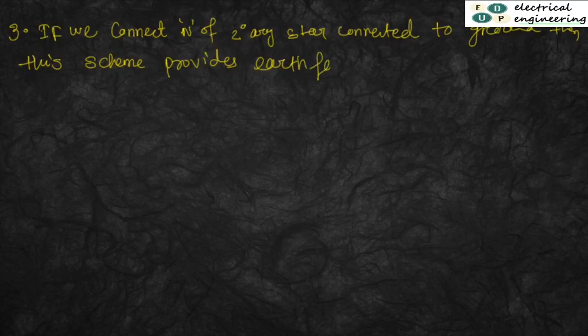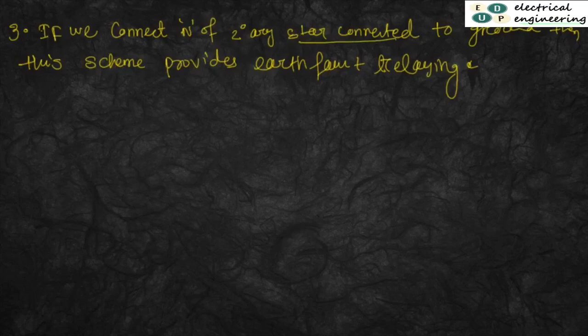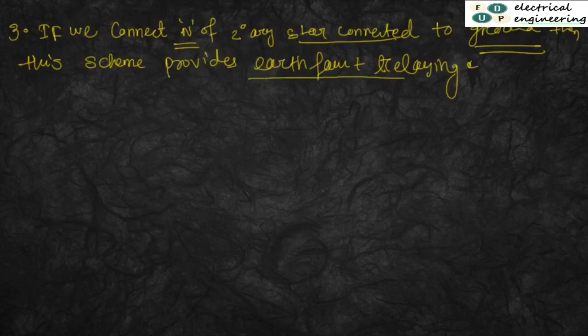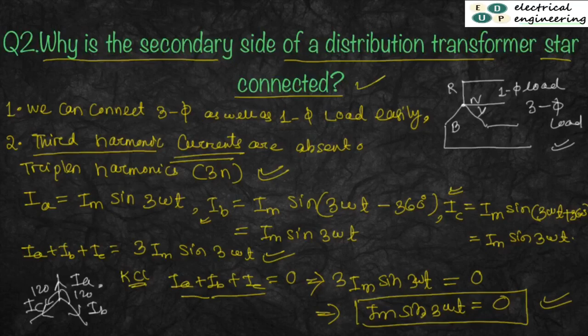Okay, now come to the third advantage. If we connect the neutral of the star connected secondary to ground, then this scheme provides earth fault relaying. Okay, so this is the internal advantage of a star connected network when we are connecting the neutral point to ground. It provides you the safety mechanism, that is, it can be used for earth fault relaying. So these are some advantages of connecting your distribution transformer secondary in star connected form.